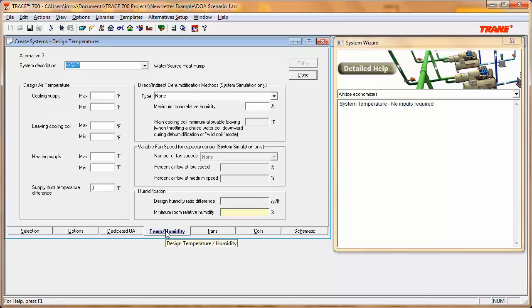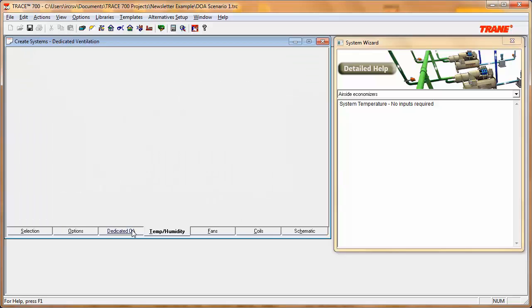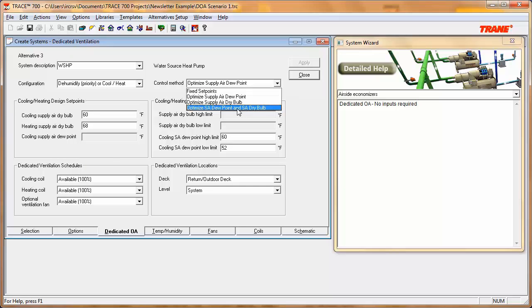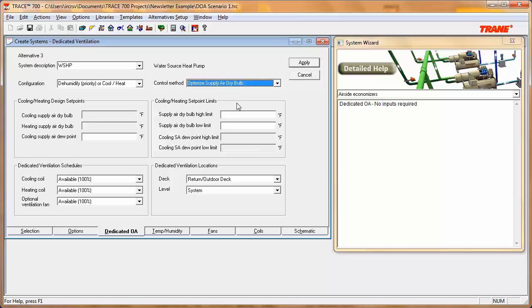We also need to go into the Temp Humidity tab and enter the maximum room relative humidity to control the supply air dew point. The other control methods I haven't yet discussed are optimized supply air dry bulb, and optimized supply air dew point and supply air dry bulb. These allow you to float the supply air temperature so that the cooling load is zero in at least one room assigned to the system — providing the right amount of cooling without over-cooling any rooms, which reduces energy consumption by minimizing reheat energy.